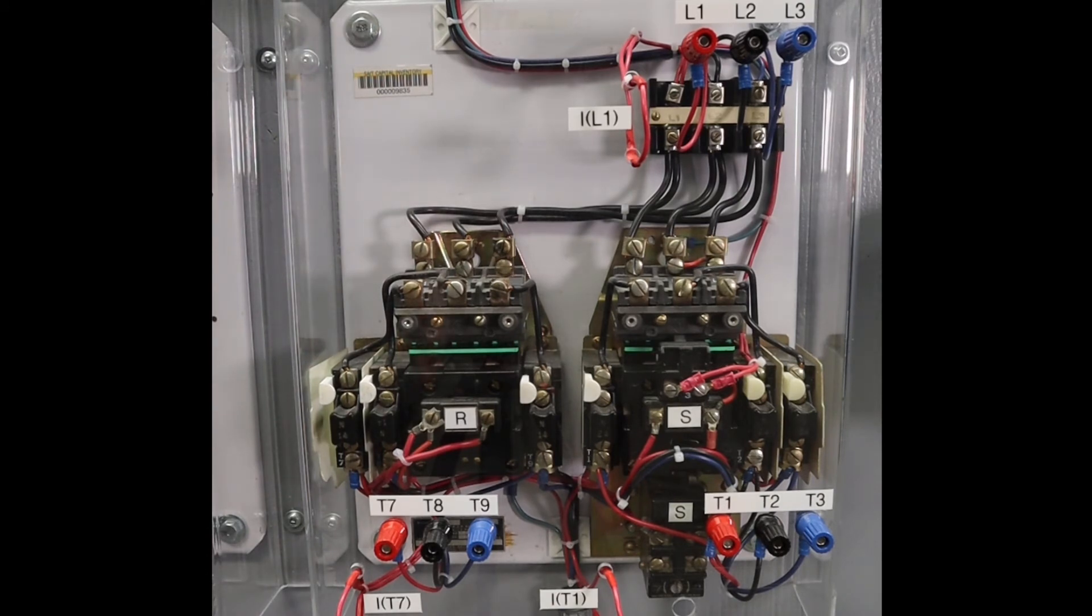This is great because we can get a reduction of current at start, about 60 percent of our full load starting current. But the problem here is we only get about 50 percent of the rated torque. So these are somewhat of an uncommon motor starter these days.